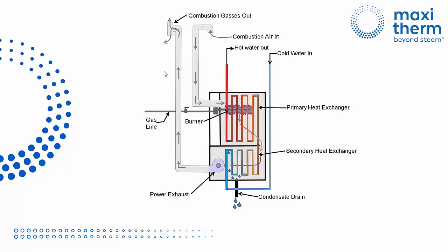This is a typical condensing boiler, which is our number one competition because most designs are going toward condensing boilers. And just a reminder of the technology, how it should operate. This is the flue gas exhaust here at the chimney, if I may say, and you want to condense the flue gas. The dew point of condensation of the flue gas is 140 Fahrenheit. So if you have a return at 160, it will never condense. So design will have a set point typically around 120 Fahrenheit to make sure the return will be around 90 or 100 Fahrenheit to make sure we will condense the flue gas.